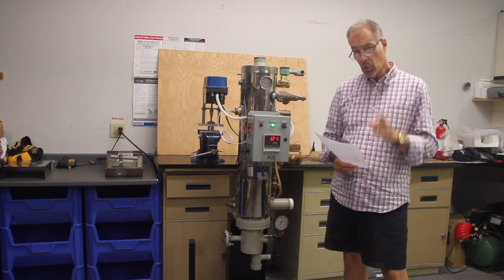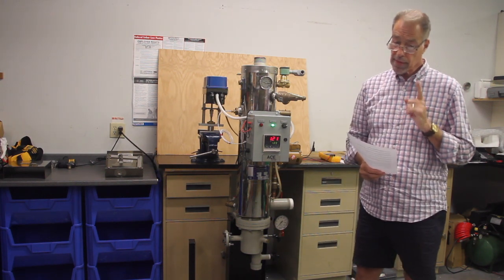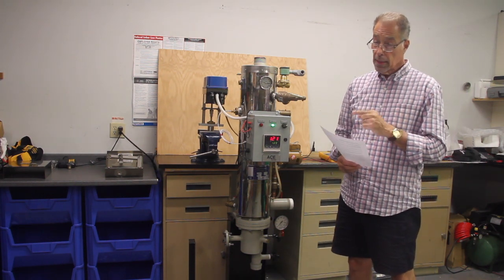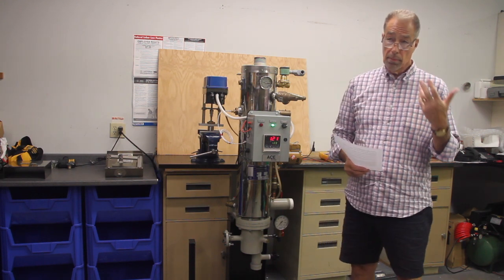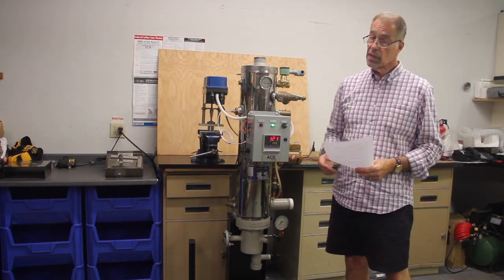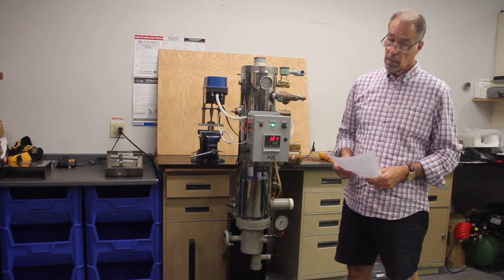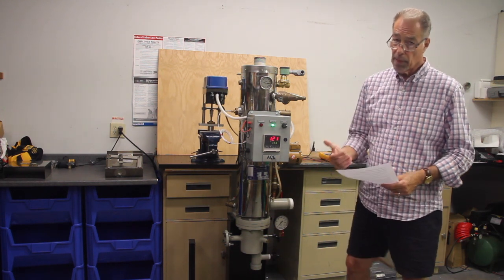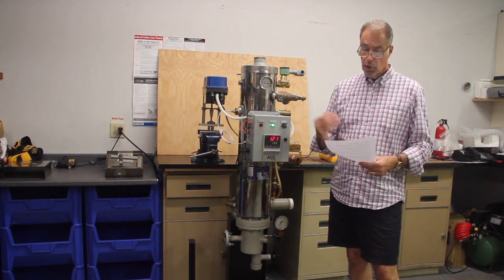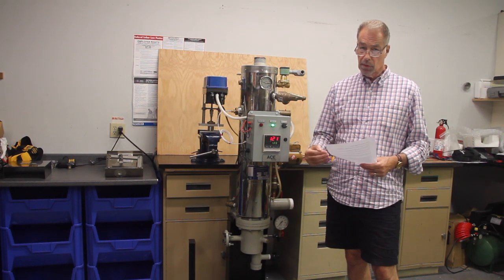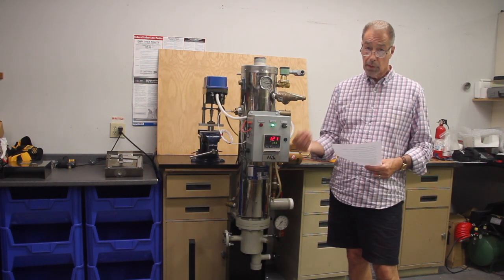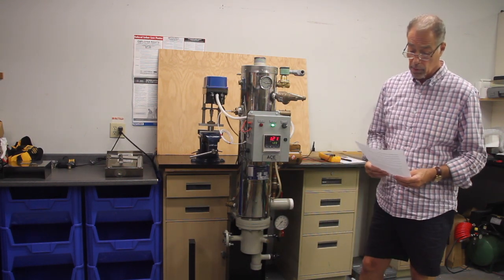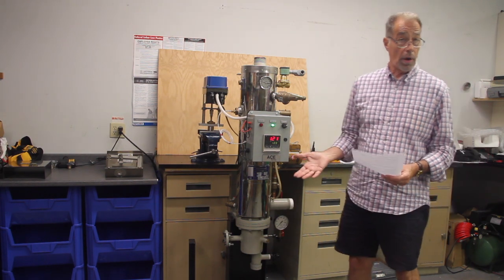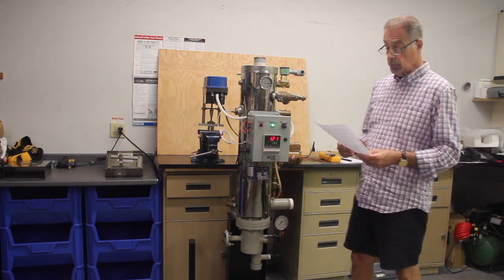Okay. The domestic heaters are each sized for 75 gallons a minute at 100-degree rise, 40 to 140, when supplied with 25 pounds of saturated steam. When I did the startup, I was up there in March, there was only 17 pounds of steam. So if you don't give us the 25 pounds of steam pressure, you're not going to have the 75 gallons a minute required capacity per the contract documents. You'll get hot water, you just won't get the full capacity.